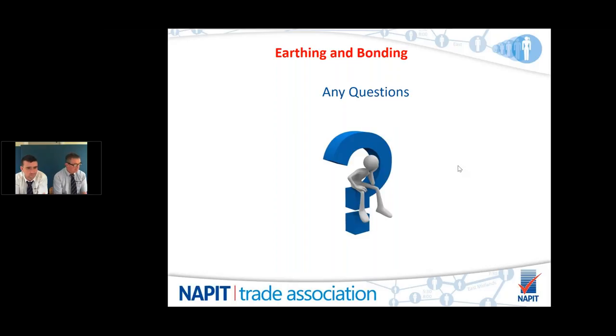Great, thank you. So we've got one from Lucien who's asking, does a lightning conductor need testing for continuity during an EICR? I'm not sure whether that's off topic or not, but one for you, sir. Lightning conductors actually come under a different British standard. Whether they actually need bonding now or not, the older regulations said that they should be bonded back to the main earthing terminal. What the regulations now state is that the designer of the lightning conductor system needs to be consulted as to whether it needs bonding. So somewhere along the line, the person who put the lightning conductor in should be asked, does it need bonding? If it's an existing installation and it's bonded already, then that is the answer.